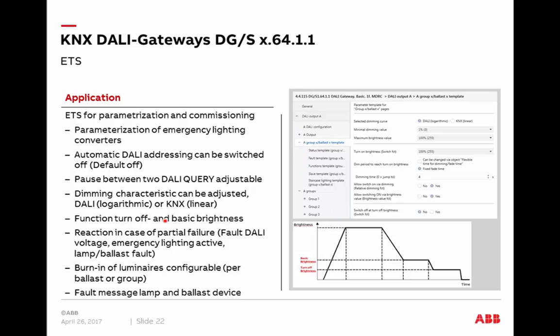The dimming characteristic or dimming curve can be adjusted as before. The standard is a logarithmic curve for smooth, even dimming for the human eye, but it can be changed to linear behavior in special cases. The turn-off brightness and basic brightness function is demonstrated with a staircase lighting diagram: the light switches on at a certain level, then dims down to a basic brightness warning level before going to a turn-off brightness rather than switching off completely. Such behavior is easily adjustable in the ETS.